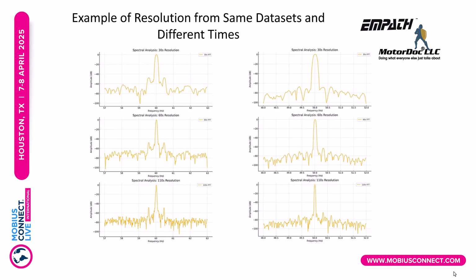Spectral analysis at 60 seconds, you can see that some of those peaks are starting to sharpen up, and there are other peaks showing up in there. And if you go down to 110 seconds, you can see that some of those peaks are actually combinations of peaks, so they appear higher or wider up top, and now they're sharper, so you can actually see other distinctions, like those peaks close to the primary peak. Those could be conditions related to slow speed components on the output of the machine. The other peaks, those are actually pole pass frequency. And then again, on the right, same type of thing.